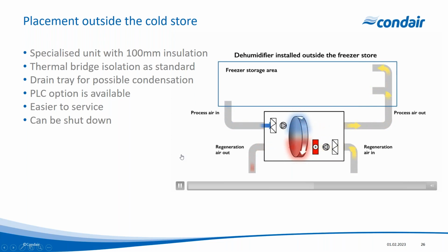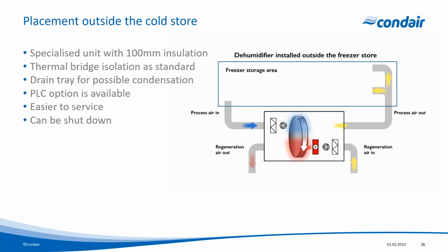So, firstly, there are a couple of things we need to consider here. We have got air at -27, potentially, maybe even colder, going into this unit, and this unit is in ambient conditions. So we've got to have 100mm insulation, so make sure that we don't get ice forming on the inside of the dehumidifier. So we have that 100mm insulation. We also have a thermal bridge isolation. So any bit of metal or any item within that casework that could be a thermal bridge and have a good heat transfer, we isolate that and insulate it to prevent that thermal bridging happening.